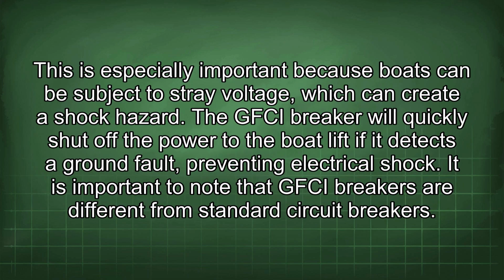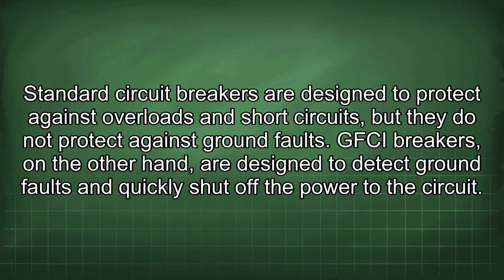This is especially important because boats can be subject to stray voltage, which can create a shock hazard. The GFCI breaker will quickly shut off the power to the boat lift if it detects a ground fault, preventing electrical shock. It is important to note that GFCI breakers are different from standard circuit breakers. Standard circuit breakers are designed to protect against overloads and short circuits, but they do not protect against ground faults.